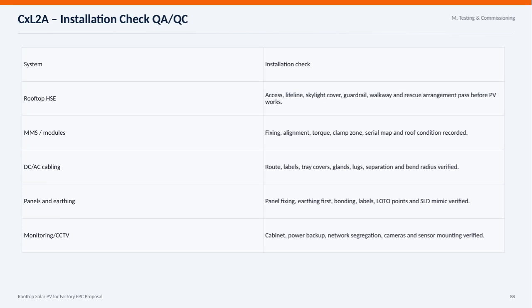Now, let's review the CXL2A installation check for quality assurance and quality control during the testing and commissioning phase of our rooftop solar PV project for the factory. Starting with Rooftop HSE, we ensure that all safety measures like access points, lifelines, skylight covers, guardrails, walkways, and rescue arrangements are properly in place and approved before any PV work begins. Moving on to the modules, we check the fixing, alignment, torque, clamp zones, serial mapping, and record the roof condition to make sure everything is correctly installed and documented. For DC and AC cabling, we verify the routing, labeling, tray covers, glands, lugs, as well as the separation and bend radius, to avoid any electrical issues.